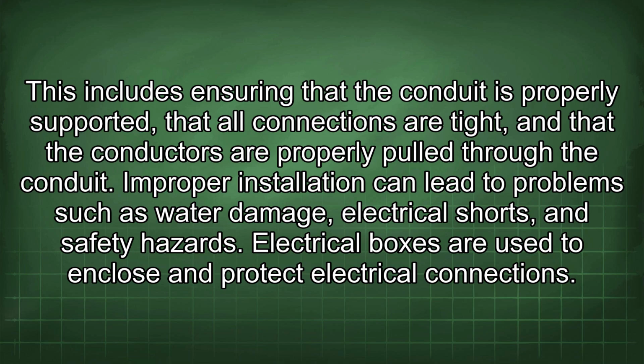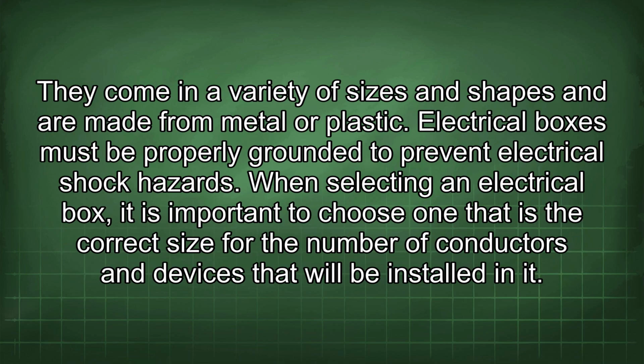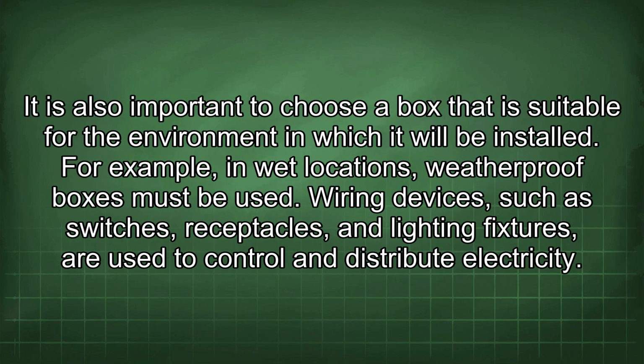Electrical boxes are used to enclose and protect electrical connections. They come in a variety of sizes and shapes and are made from metal or plastic. Electrical boxes must be properly grounded to prevent electrical shock hazards. When selecting an electrical box, it is important to choose one that is the correct size for the number of conductors and devices that will be installed in it. It is also important to choose a box that is suitable for the environment in which it will be installed. For example, in wet locations, weatherproof boxes must be used.